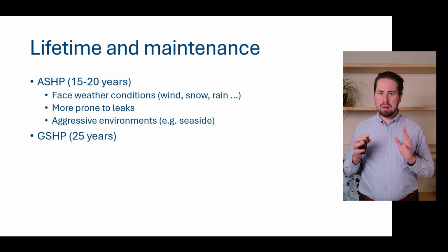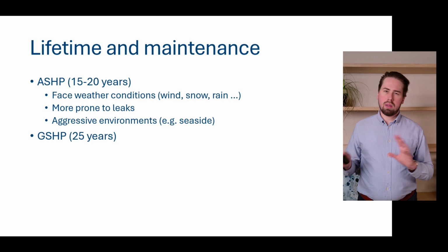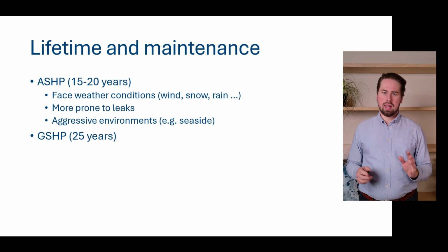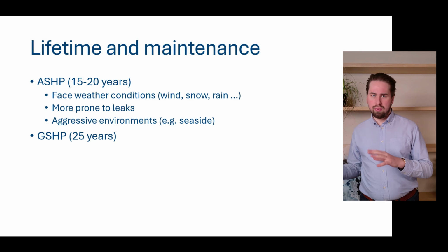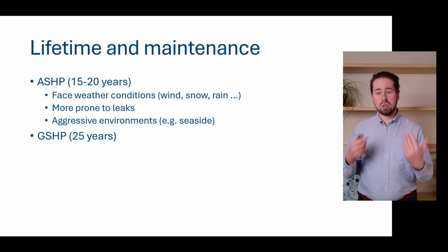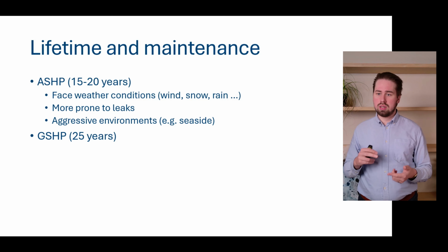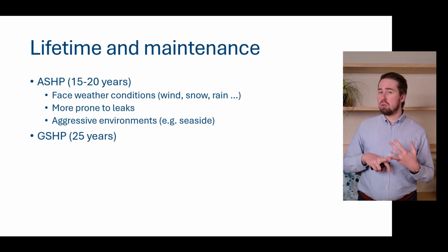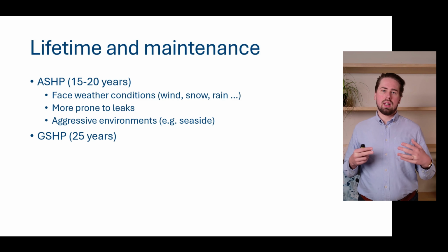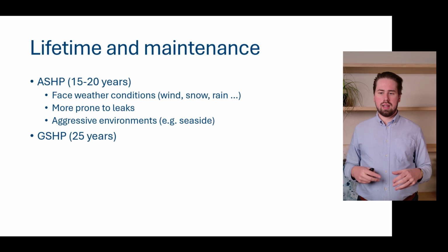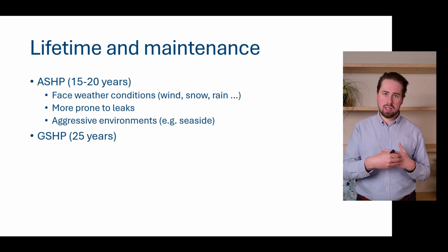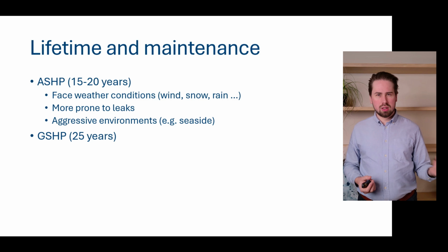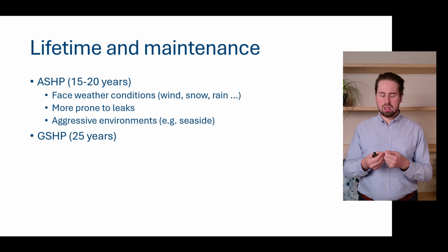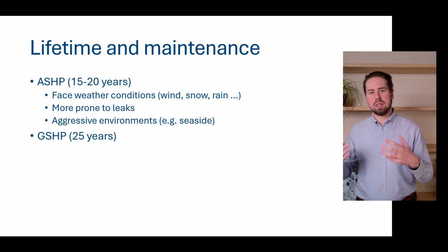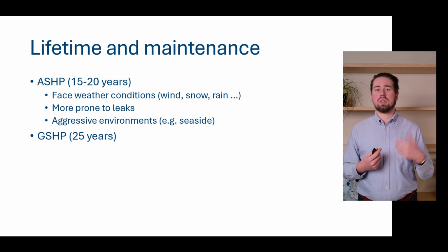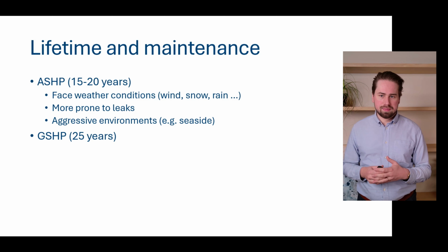Now, talking about lifetime and maintenance, it's a little bit vague and depends from manufacturer to manufacturer, but typically air source heat pumps have a lifetime of between 15 to 20 years. And that's because they are outside. They face the weather conditions, snow, ice, rain. They're more prone to leaks because of this. And they also are placed sometimes in aggressive environments. For example, if you live nearby the coast, there's quite a lot of salt in the winds, and this can cause the heat exchangers to corrode. So you have to install special heat exchangers that can cope with this, which is also more expensive.